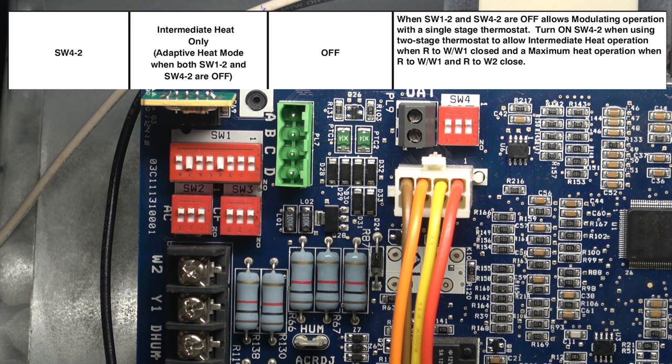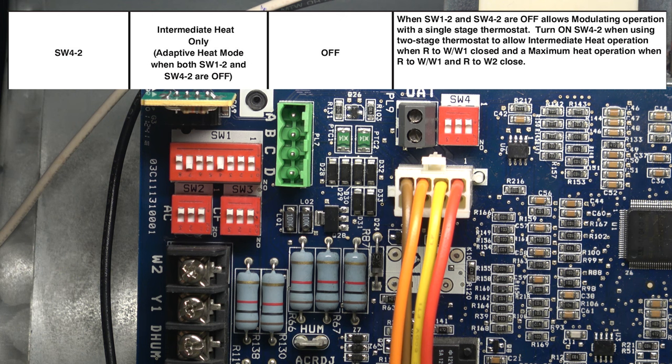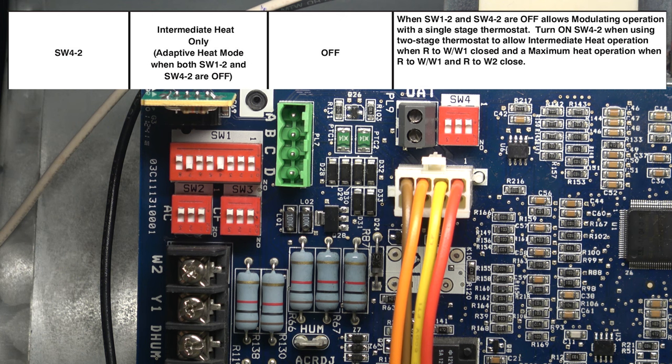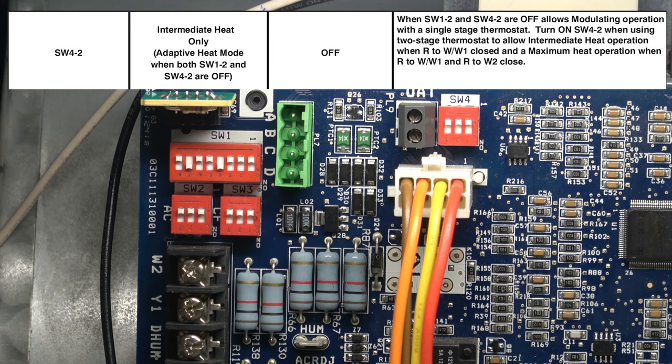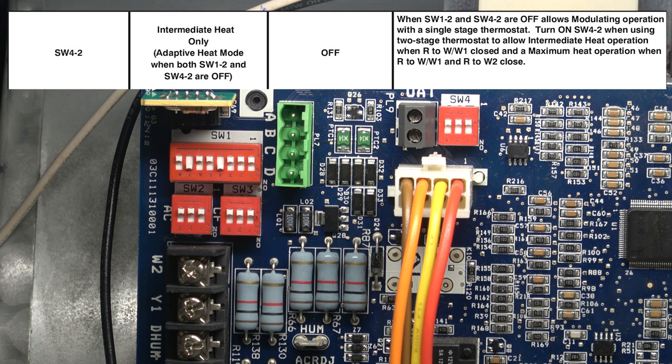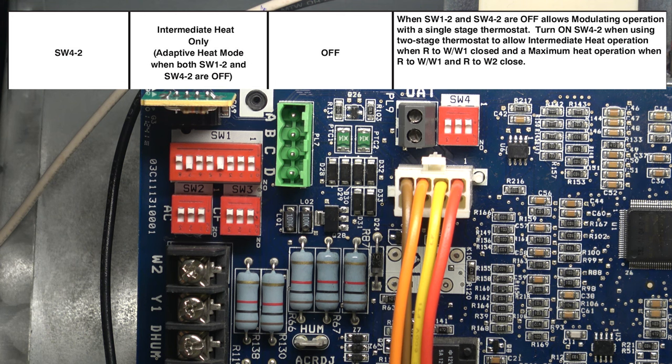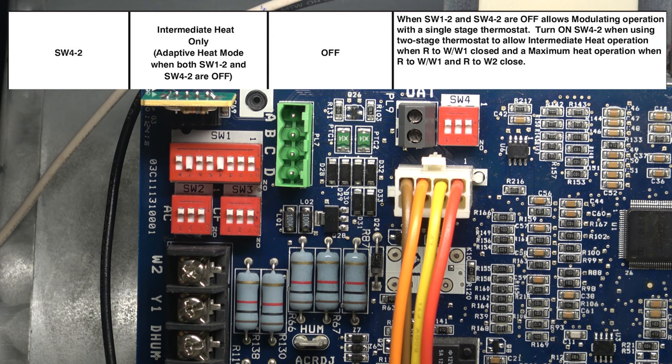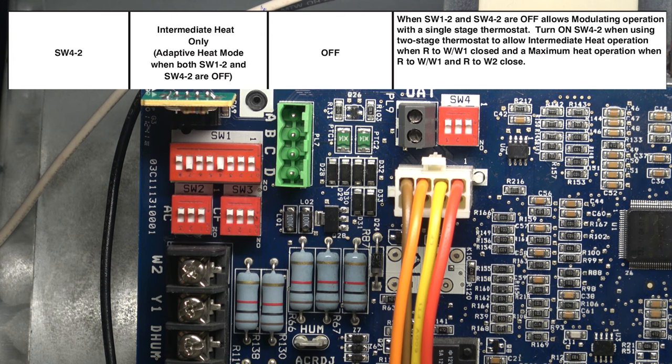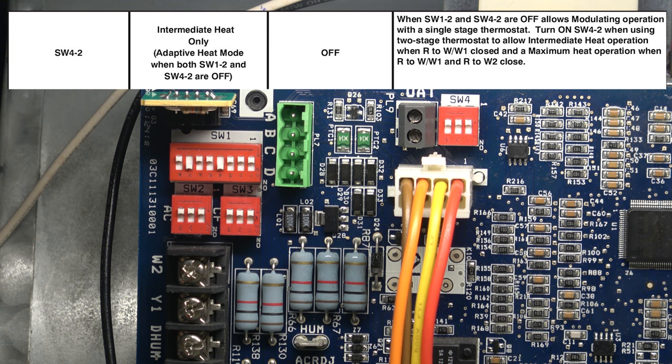Turn on switch four number two when using a two-stage thermostat to allow intermediate heat operation when R to W1 is closed. Switch four number two works with switch one number two.